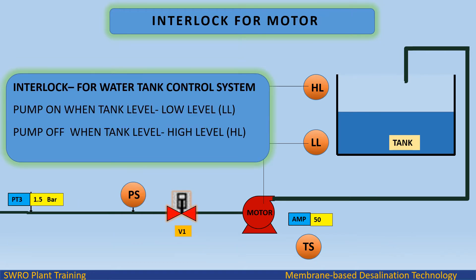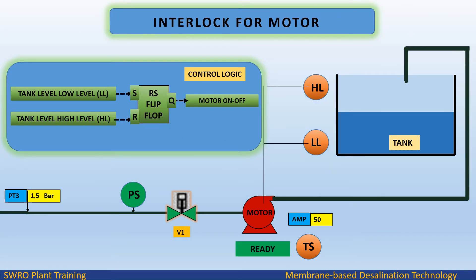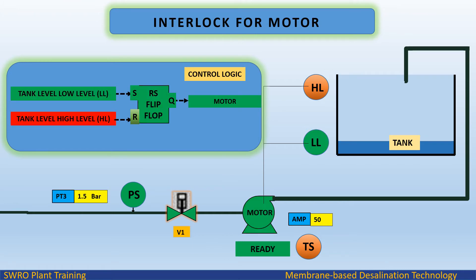Interlock for motor — interlock for water tank control system: pump on when tank level reaches low-low (LL); pump off when tank level reaches high level (HL). Control logic uses RS flip-flop set and reset. When tank level low is active, it sets the RS flip-flop and the motor turns on.